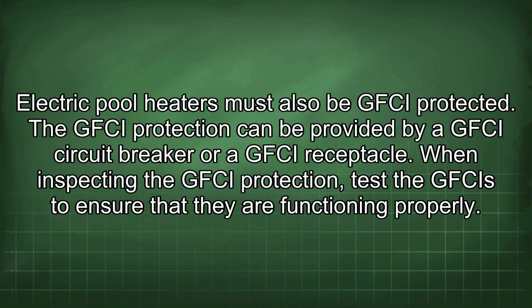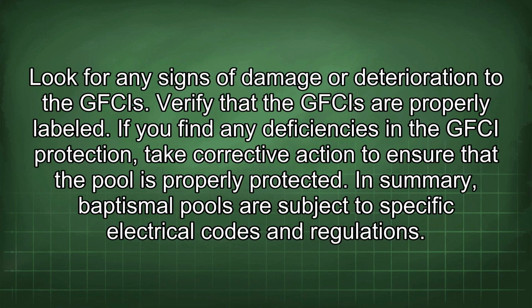The GFCI protection can be provided by a GFCI circuit breaker or a GFCI receptacle. When inspecting the GFCI protection, test the GFCIs to ensure that they are functioning properly. Look for any signs of damage or deterioration to the GFCIs. Verify that the GFCIs are properly labeled. If you find any deficiencies in the GFCI protection, take corrective action to ensure that the pool is properly protected.